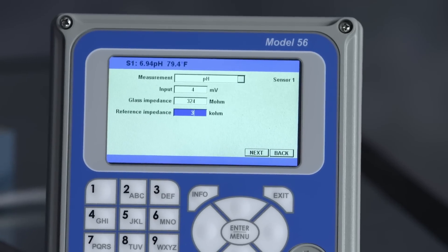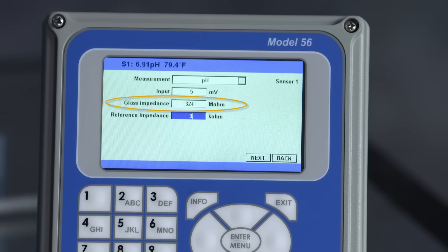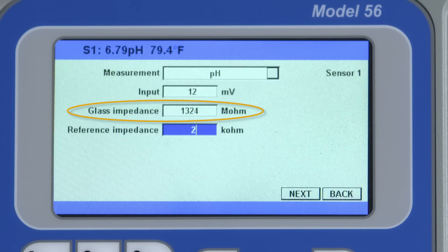Many of our pH sensors have a nominal glass impedance between 50 to 1000 megaohms, although the exact value isn't critical. A large upward step change would indicate a coated glass bulb or dry sensor.